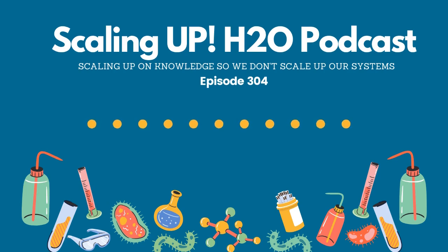Folks, corrosion coupons have a couple of things that we measure. One, it's the weight over a specific amount of time. So how much metal is lost from the beginning date to the ending date? If we don't have the starting weight and we don't have the date that the coupon was put into the system and the date that the coupon was taken out of the system, we simply can't measure the coupon. Now, I can tell you how much the coupon weighs because that is our final step in the lab, but that's all I can tell you, and that's not enough data, and that is a useless coupon.